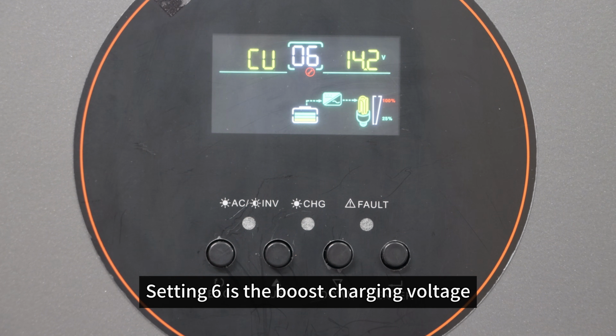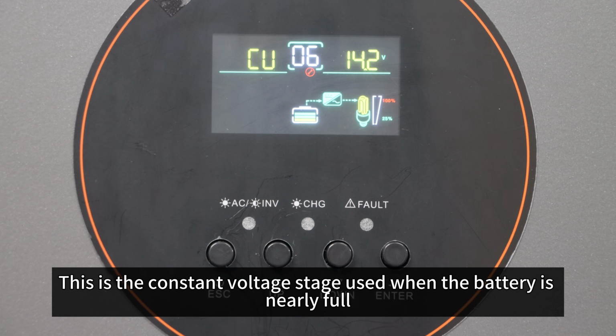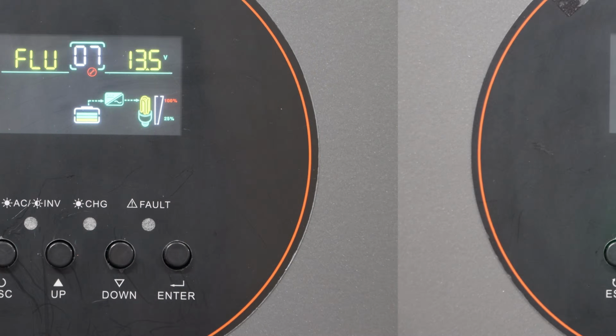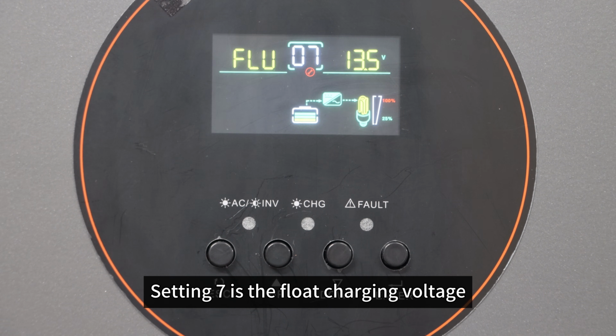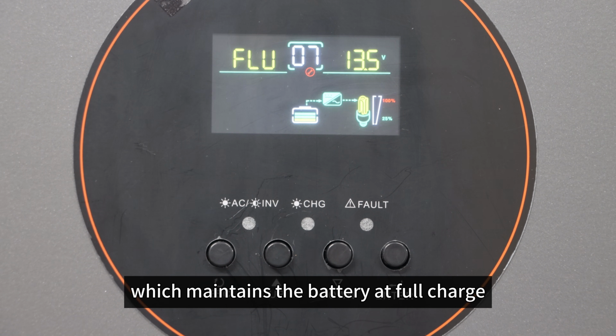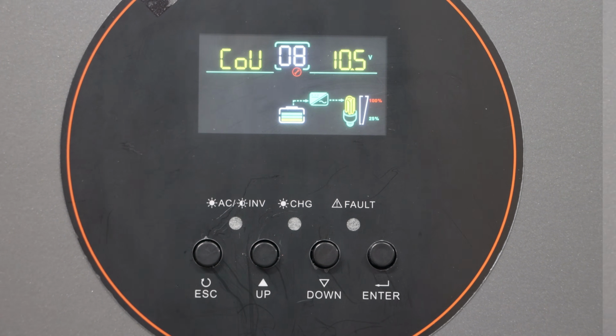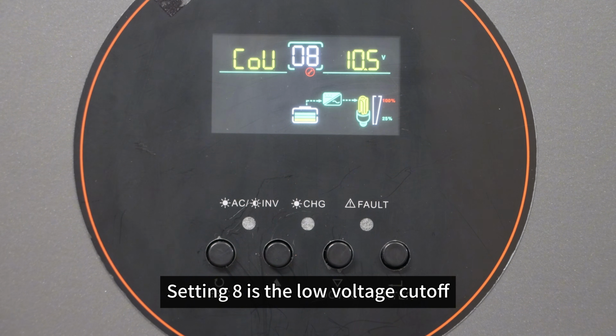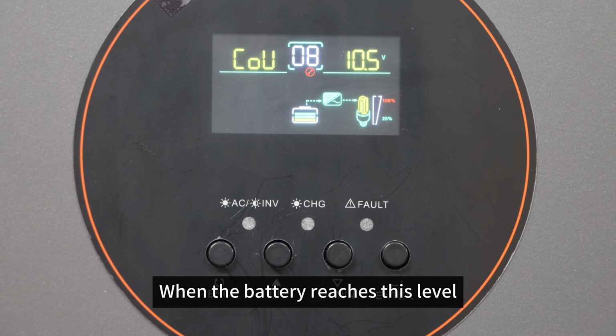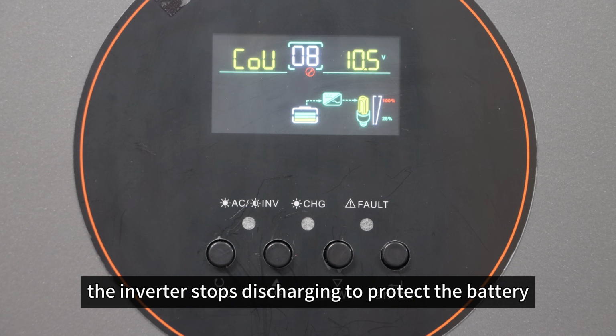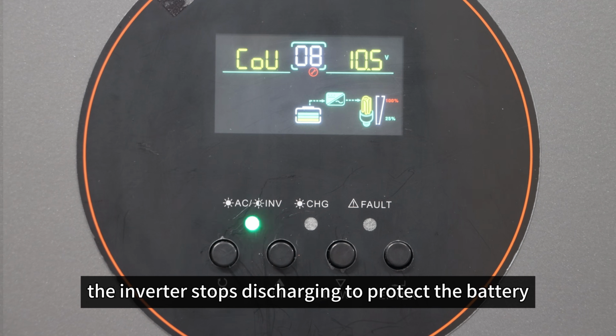Setting 6 is the boost charging voltage. This is the constant voltage stage used when the battery is nearly full. Setting 7 is the float charging voltage, which maintains the battery at full charge. Setting 8 is the low voltage cutoff. When the battery reaches this level, the inverter stops discharging to protect the battery.